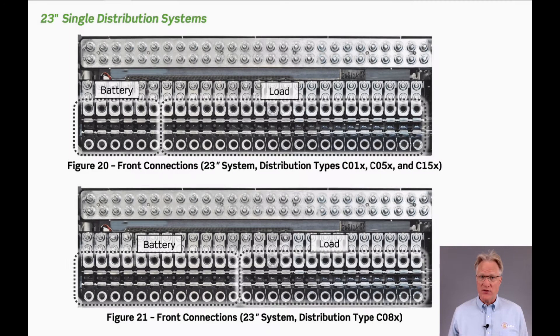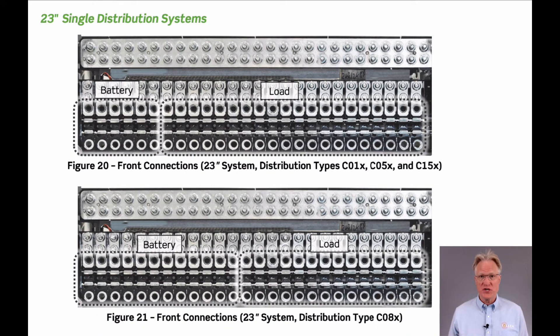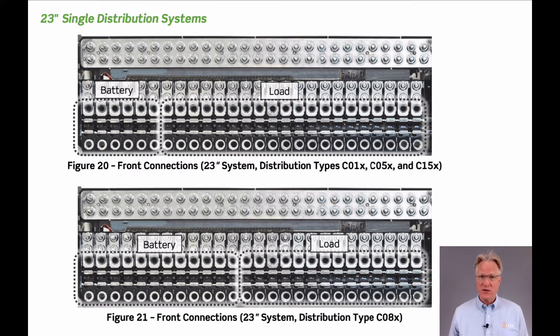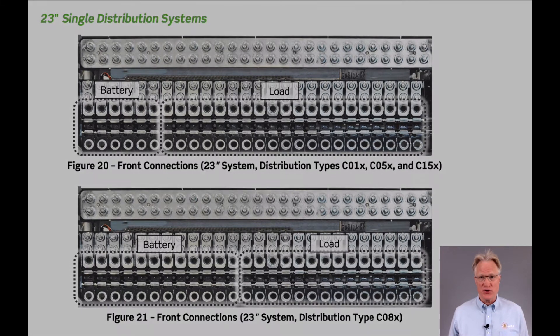The 23-inch distribution options include six battery breakers with a shunt only, or six or twelve battery breakers with a low voltage disconnect. All 26 breakers can be load only, or 20 or 14 load breakers if battery breakers are used.